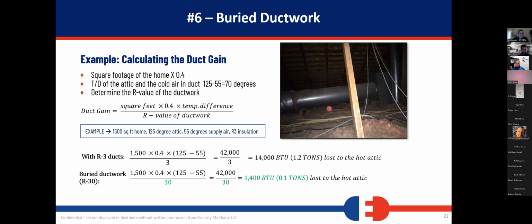So we do the math again. Now we're down to 1,400 BTUs being required from the system to keep the ducts neutral. At this point, we've saved over 1 ton of cooling capacity. So on a typical 1,500 square foot house with old ducts in the attic space and a 3-ton system, which is what it would have had when it was built in the 70s, we can now reduce that by at least 1 ton just based on fixing and burying the ductwork. So it's a really easy thing, and it makes the house more efficient as well.